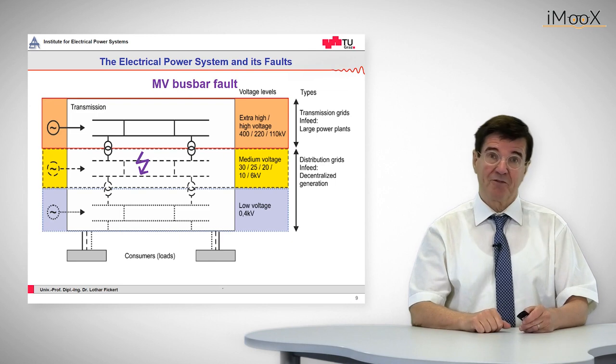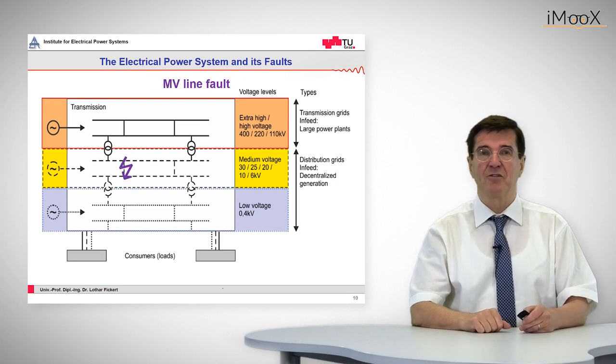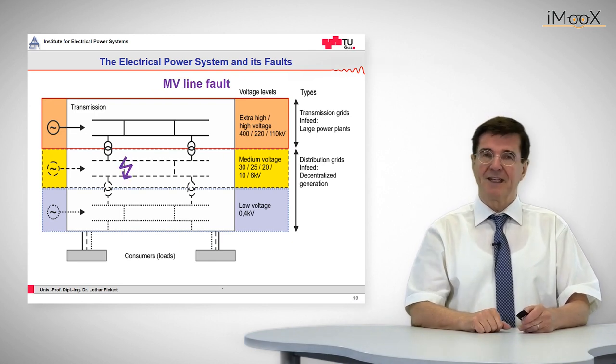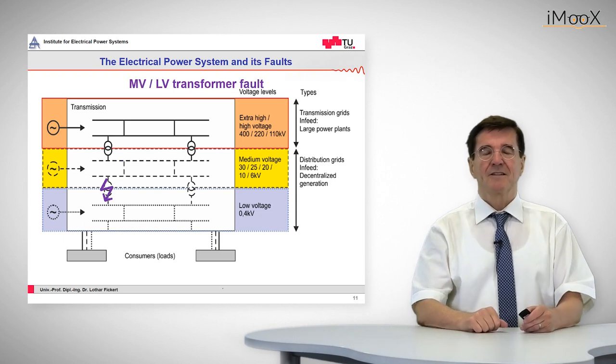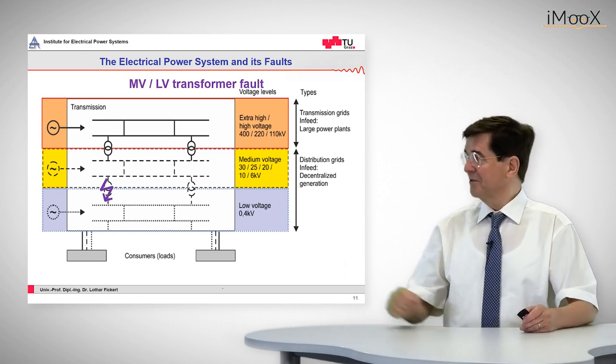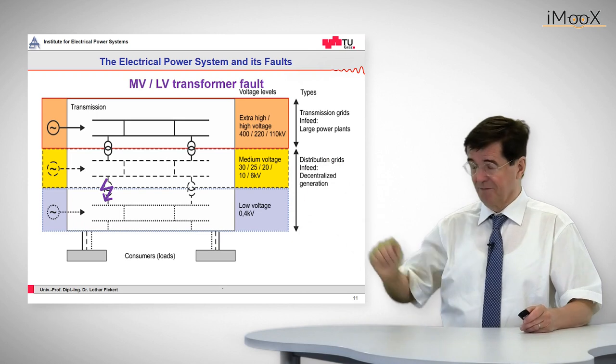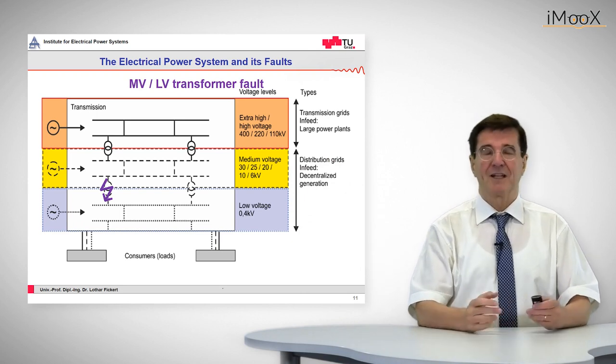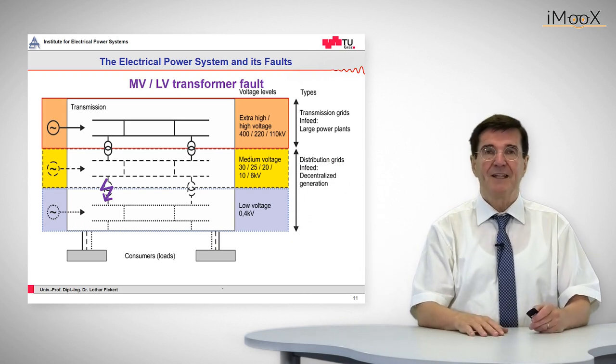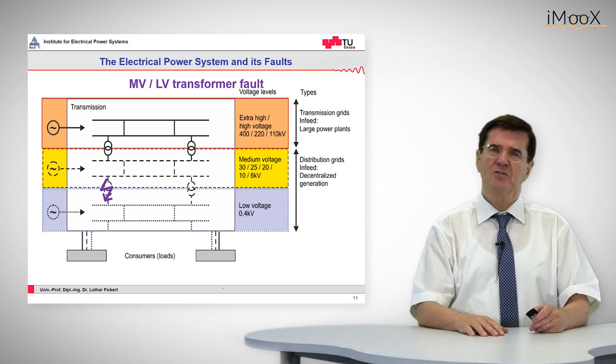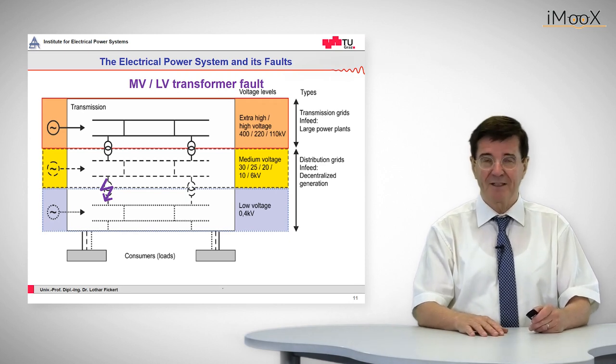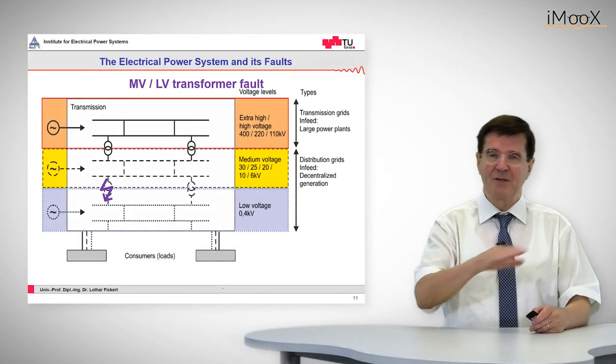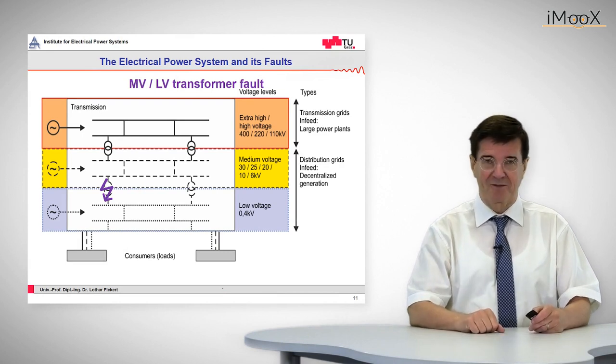We can also have bus bar faults, line faults, and faults in the transformers between medium voltage and low voltage. These transformers are usually located in ring main units, and since the low voltage system is typically made up as radial networks, such a fault trips the consumer's electricity supply.